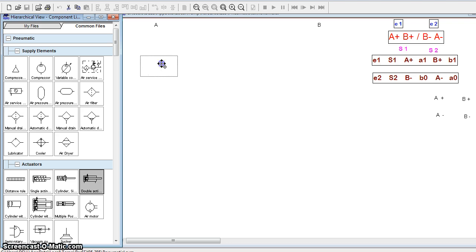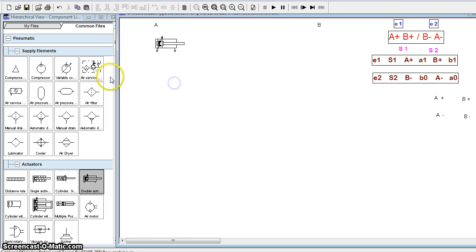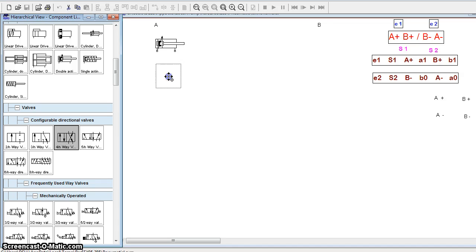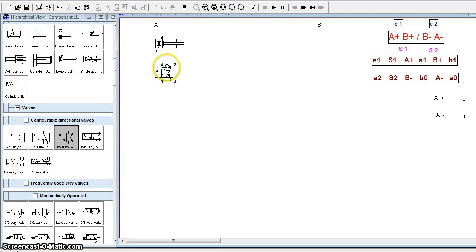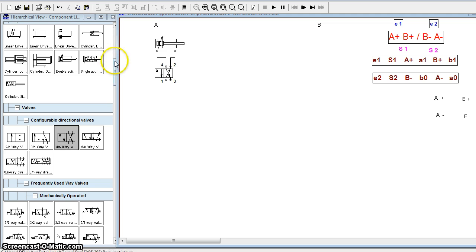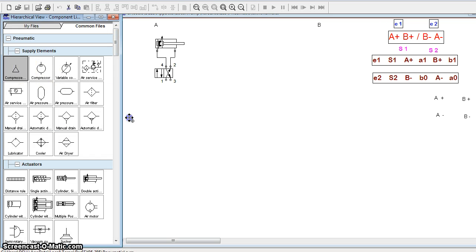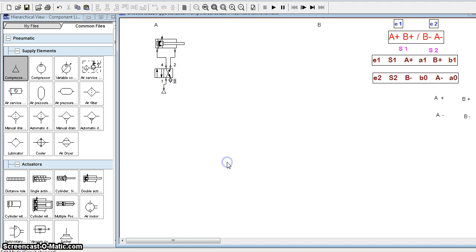First, we will select a double-acting cylinder and a valve to operate it. For that we will use a 4/2 DC valve. When this valve is activated, fluid should flow to the cap end of the cylinder and return from the rod head end. This valve connects to the compressor, operates the cylinder, and the exhaust port connects to the exhaust — we can also use a silencer for that.